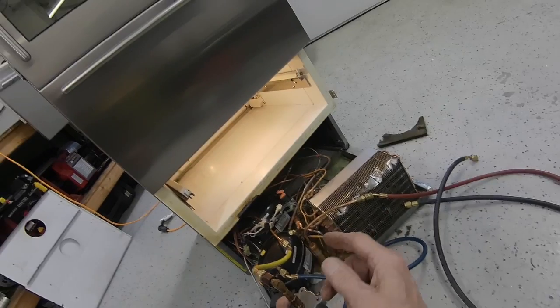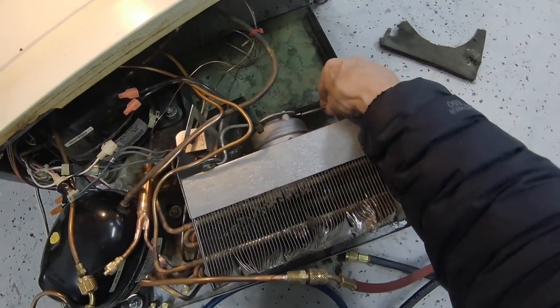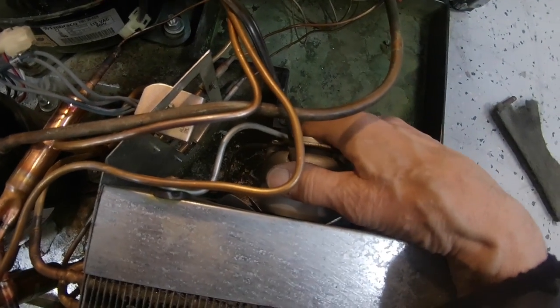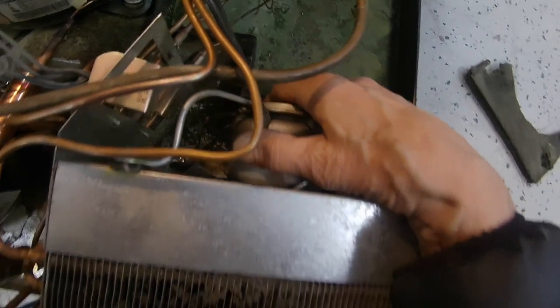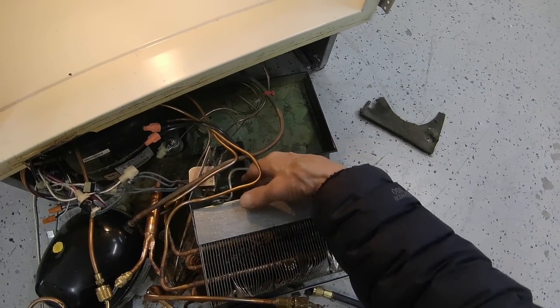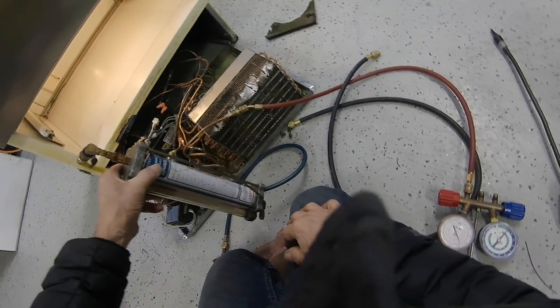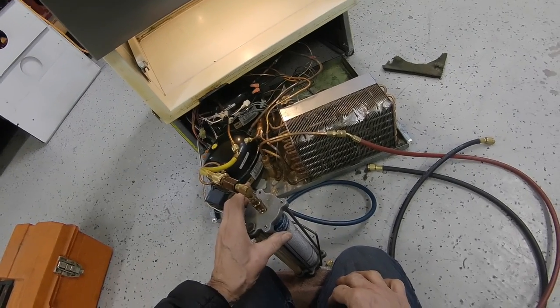The rest of the machine — I have to fix the wiring section — but there's one other problem with this unit: the condenser fan motor, which I disconnected. You see that bolt? There's no nut on the end of it — it broke off or it's not on. So this unit was making a little bit of a racket, a little vibration noise. I'm going to take the condenser fan motor out and fix that so we get a nice tight fit. Let's finish charging this up and move on to the next project.